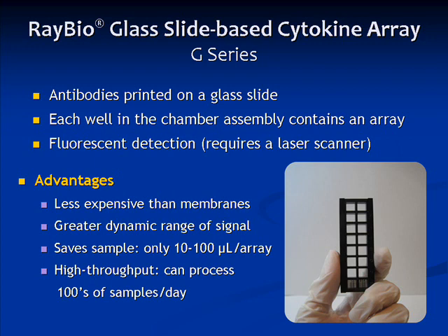The G-Series has several advantages over the C-Series. For one, it's less expensive than the membrane-based arrays. It also has a wider signal range. And it's more economic in terms of sample — only 100 microliters is required per array, while the membrane-based arrays require up to 1 ml. The G-Series is also amenable to high throughput. The slides are very easy to handle, and one can easily process several hundred samples per day.